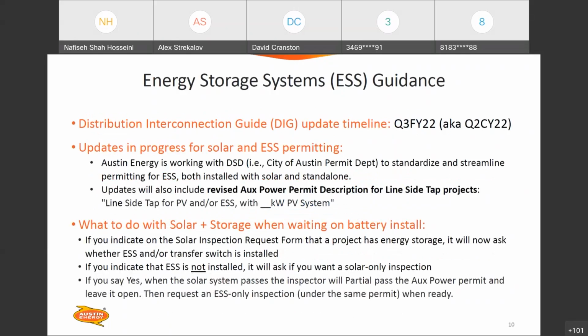So a little bit of intro to energy storage systems guidance. This continues to change as we see more ESS out in the field, and as we continue to fully embrace the code surrounding ESS installations, and we're continuing to sync up with the Austin Fire Department about their concerns about safety. Remember that we are in the process of updating the distribution interconnection guide again, and those updates will include more information and guidance on energy storage installations in the next iteration. Our expected timeline for that is the second quarter of this calendar year. So that is in progress.